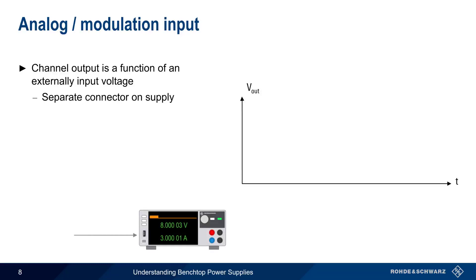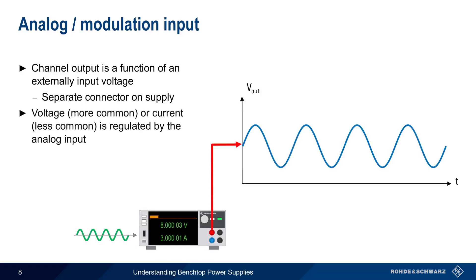On some supplies, it's also possible to control the channel output using an external input voltage. This analog, or modulation input, is fed into the supply using a separate connector. The output voltage, or sometimes the output current limit, is controlled or regulated by this analog input. As shown here, this can be used to create modulated output voltage waveforms, such as the sine wave shown here.